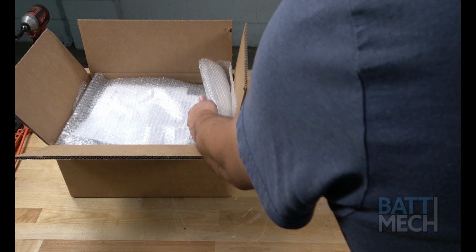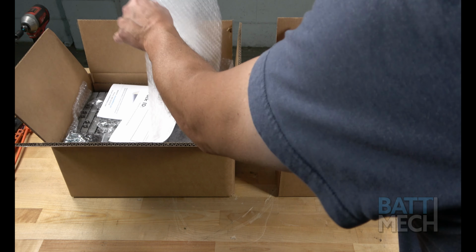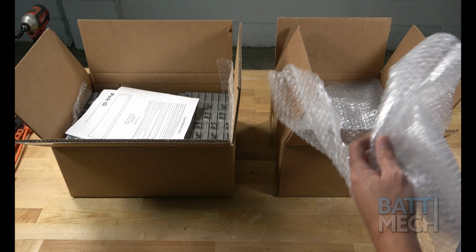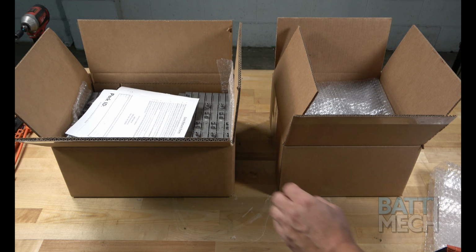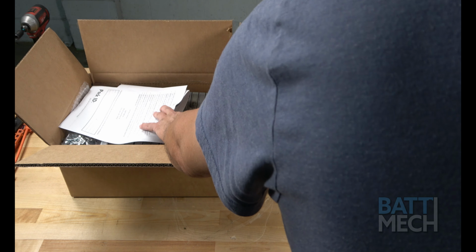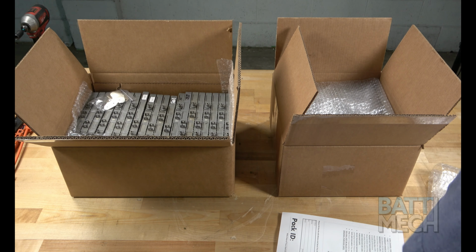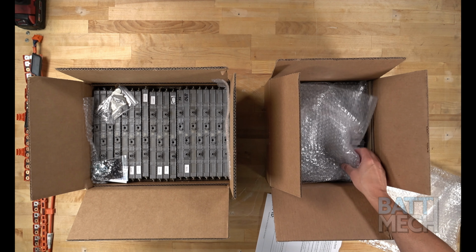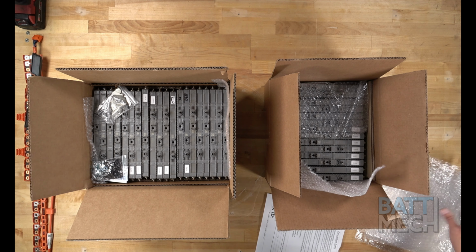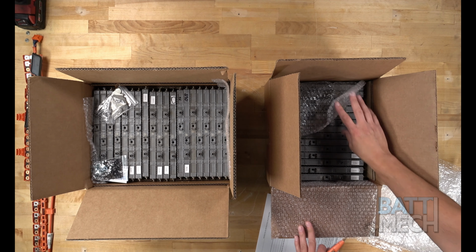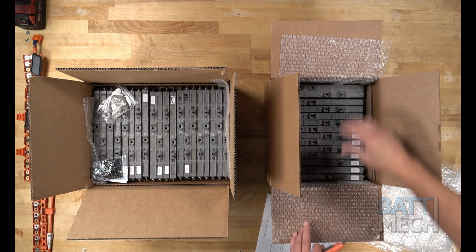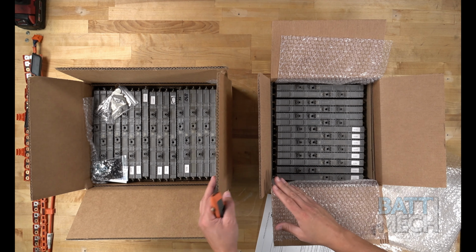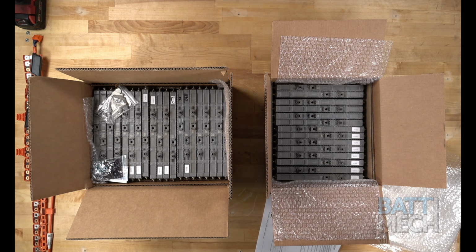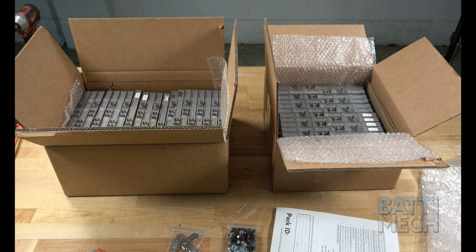Your BattMech batteries are individually tested to assess leaks, capacity, voltage, and internal resistance. The highest and lowest capacities are arranged in ways to optimize the pack's performance and to optimize the differences in block voltage throughout the pack. Each pack is load tested at the same time, but BattMech monitors the voltage of each individual module when testing. Packs are tested under a high current load.